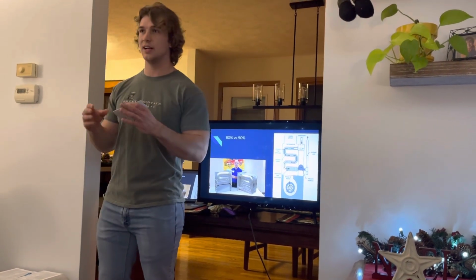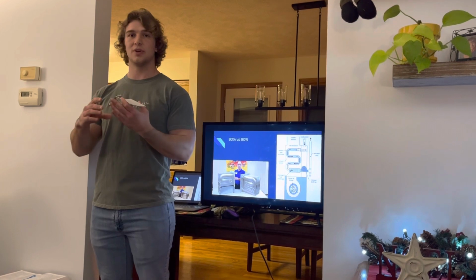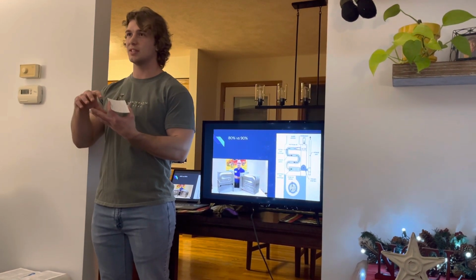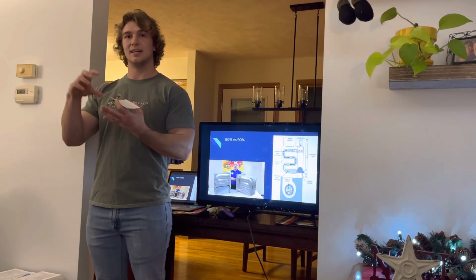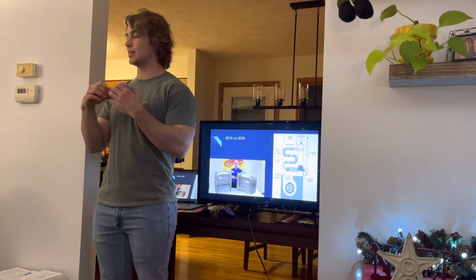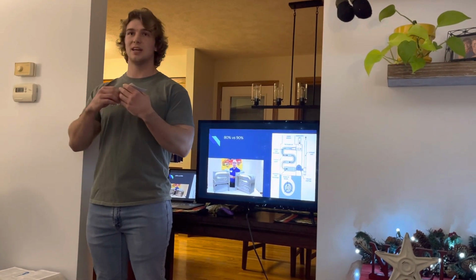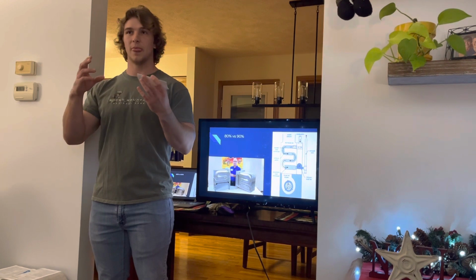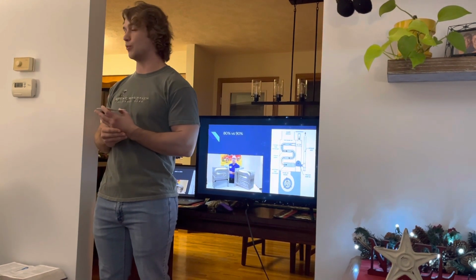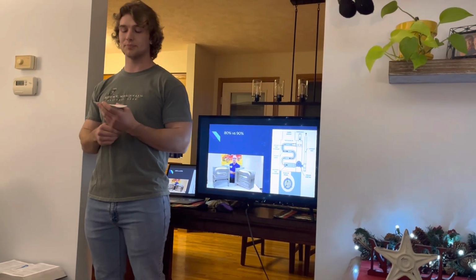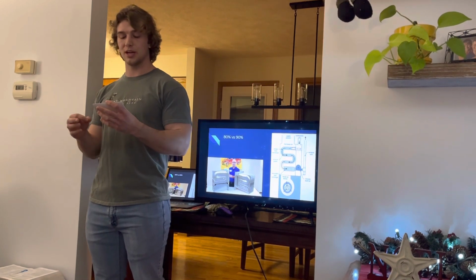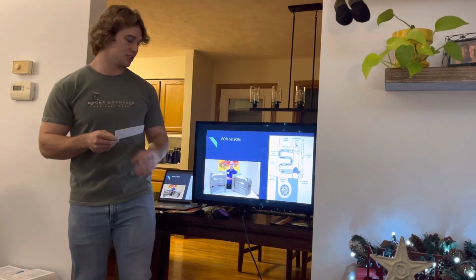In your secondary, it allows for flue gas to accumulate. As this gas accumulates in the secondary heat exchanger, it condenses, and as the gas condenses, it releases more heat that is then able to be dispersed throughout your home. This is heat that an 80% furnace would have vented to the outdoor air. Now, a 90% also has a sealed combustion chamber.